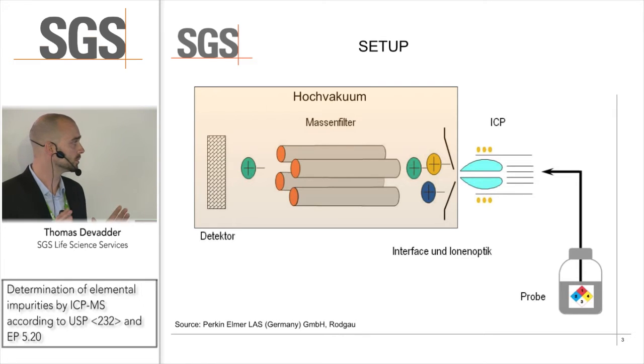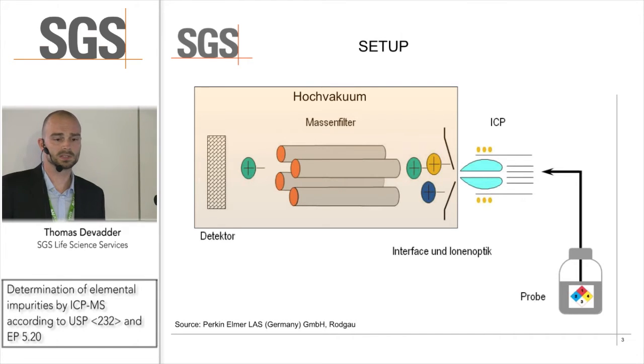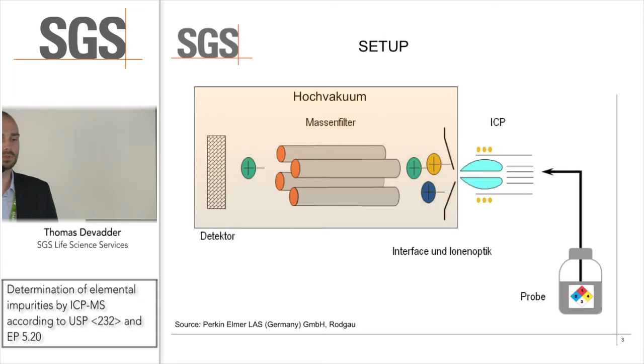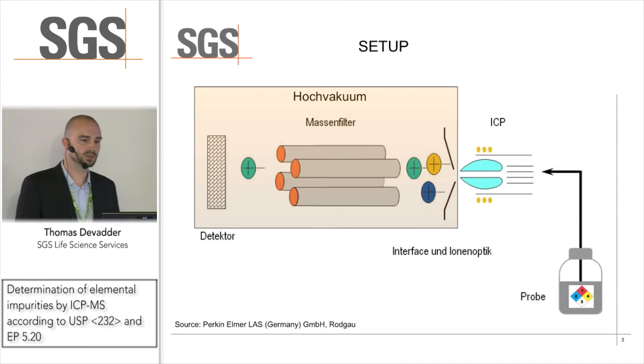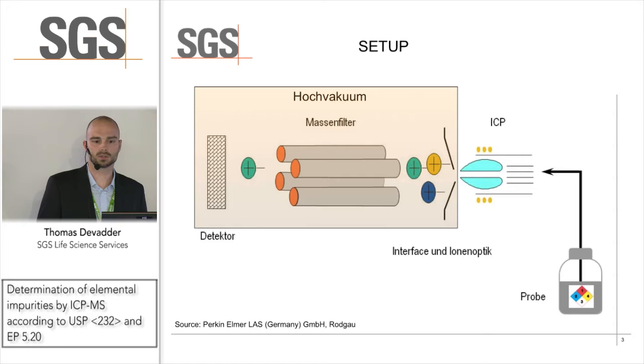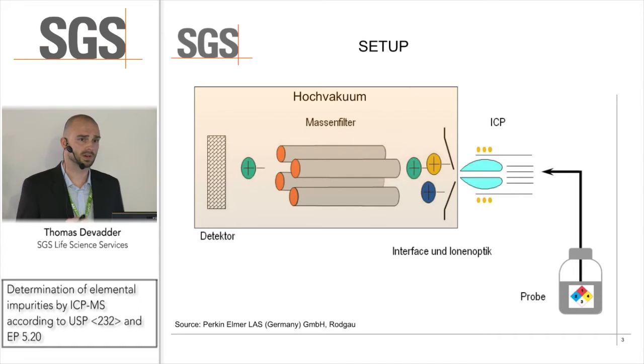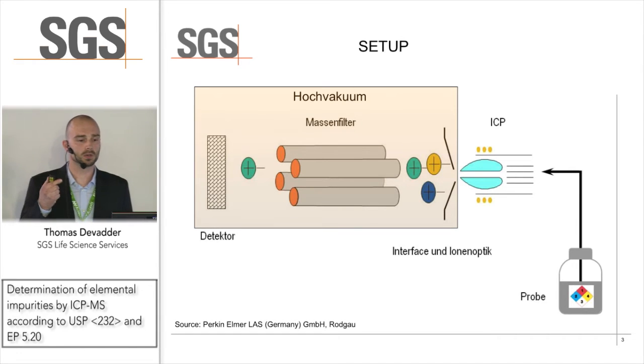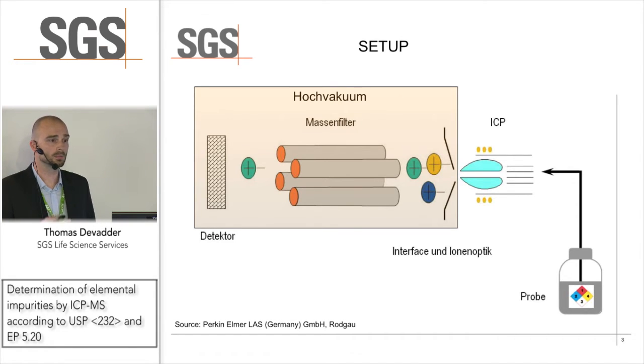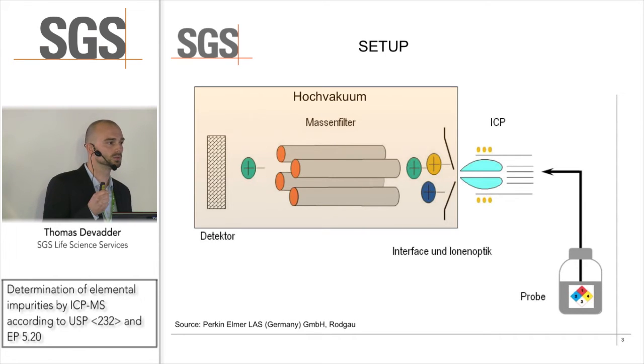When we're talking about quadrupole ICP-MS, all instruments come with the same comparable setup. We have to get our solid sample into a liquid form, transfer it into the spray chamber, and generate an aerosol using argon and transfer it into the plasma. The plasma itself has about five to ten thousand degrees and we generate positively charged ions, which are forced into the vacuum chamber by an ion beam. We separate the isotopes by the quadrupole, and at the end the detector is able to determine every single ion hit that comes from the sample.